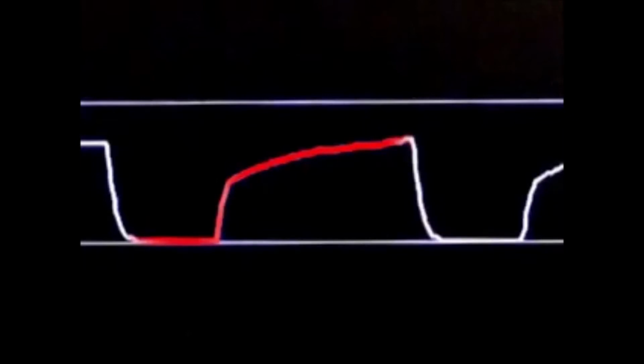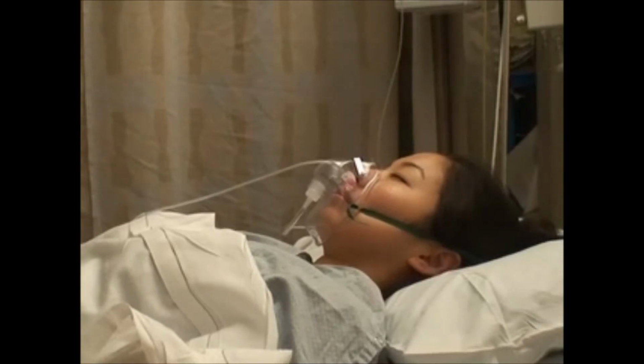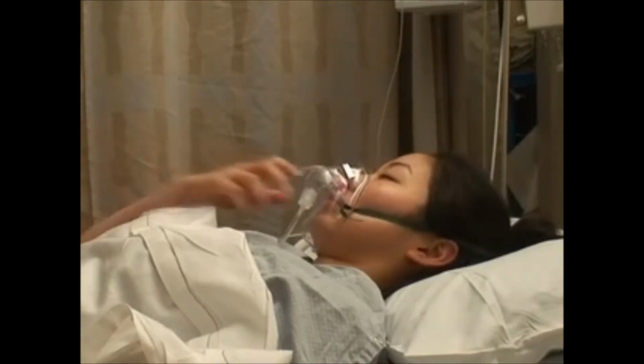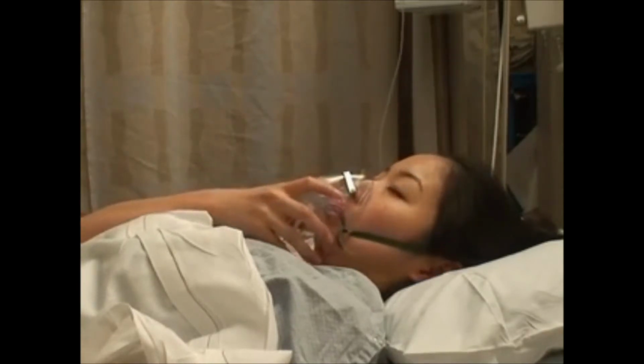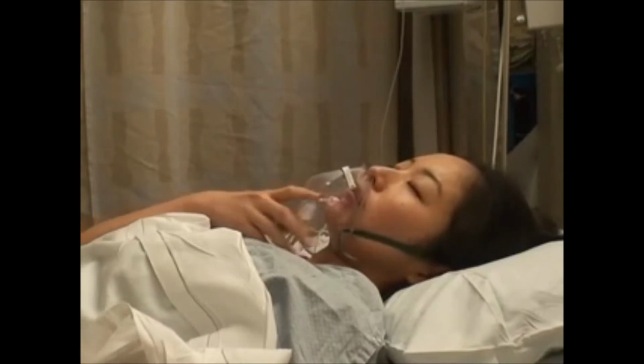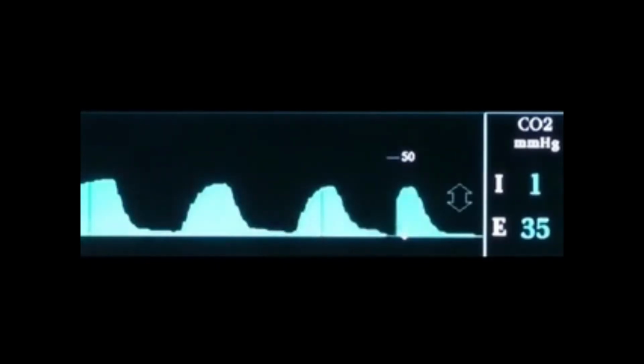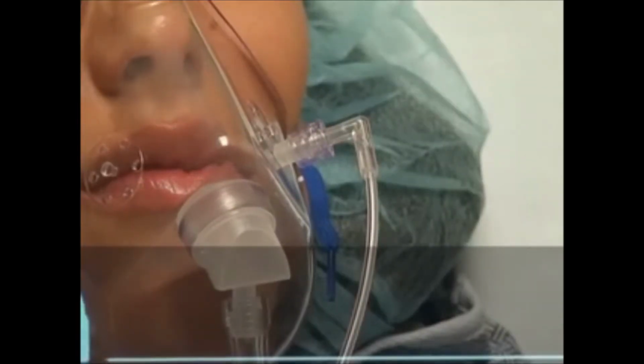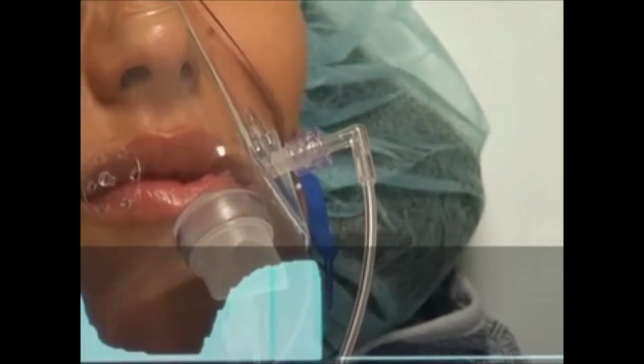The peak concentration reached at the end of exhalation is the EtCO2. As the patient begins to inhale again, the capnogram falls rapidly to 0, indicating the absence of carbon dioxide in the inspired gas. In patients who are not intubated, the samples of the exhaled gas are mixed with the surrounding atmosphere and fresh gas flow, diluting the concentration of carbon dioxide. As the side-stream catheter is moved farther away from the patient's airway, the EtCO2 value will decrease progressively. Although the EtCO2 of a patient who is not intubated represents only a qualitative indicator of ventilatory status, the patient's respiratory rate can still be determined from the waveform of the capnogram.